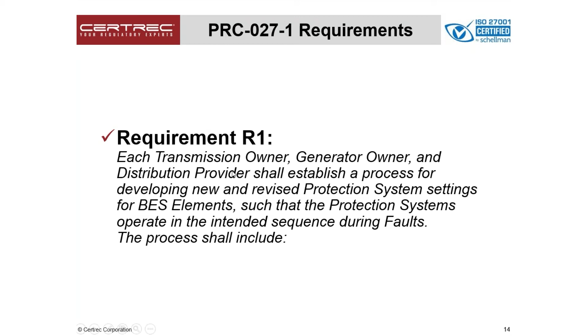Starting with Requirement 1, straight from the PRC standard: everyone shall establish a process for developing and revising protection system settings. This is probably the main one you need to come up with when first getting into the PRC and establishing it—you want to set up how you're going to set it up and control it.